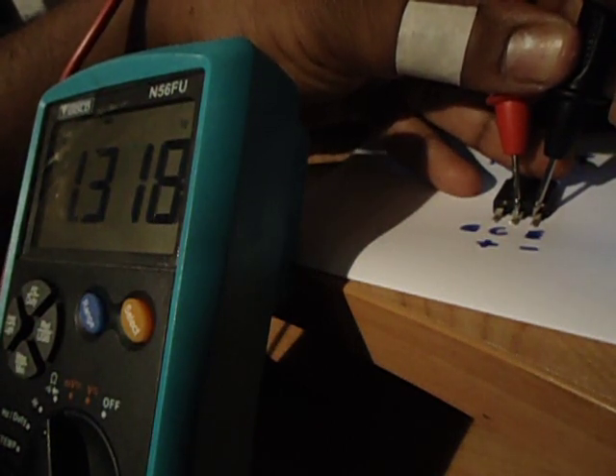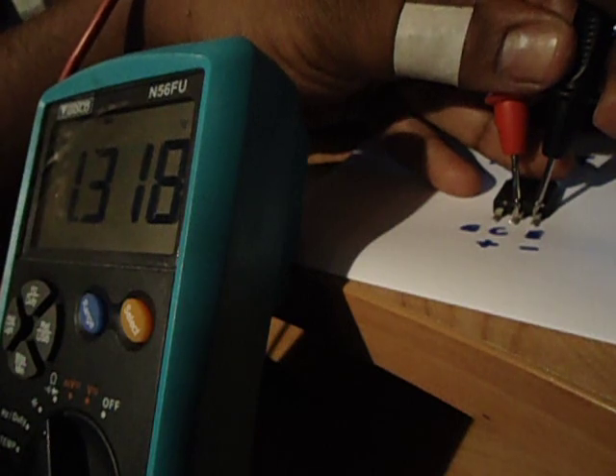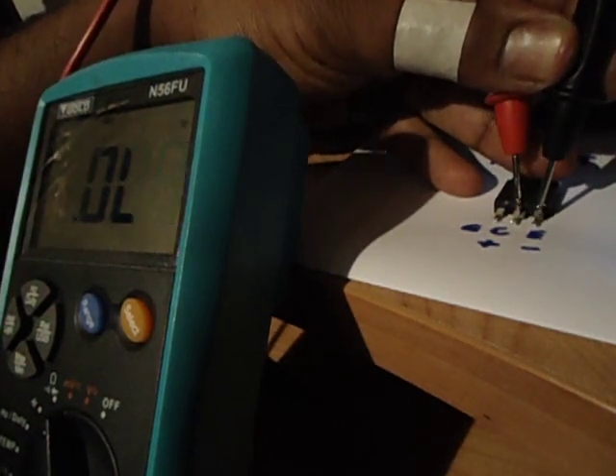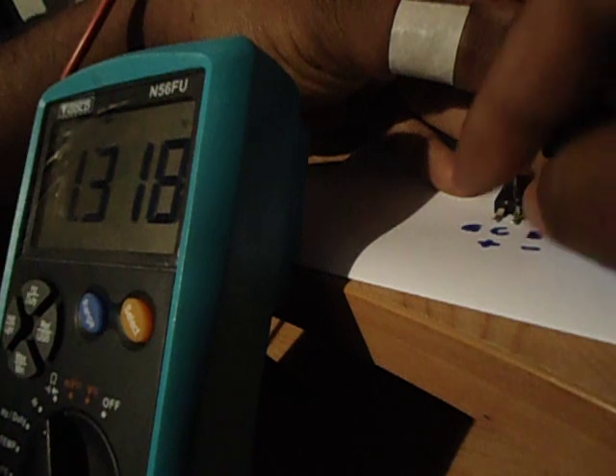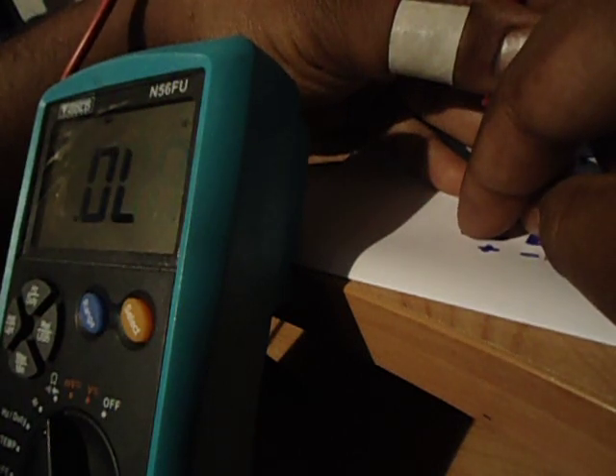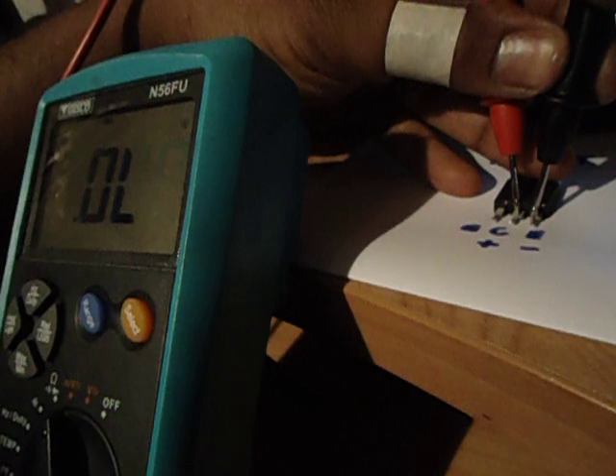If you have one where you touch the gate, you go back to the collector and there's a reading there, but you touch the gate and emitter and it doesn't discharge, like so, then you've got a faulty IGBT.